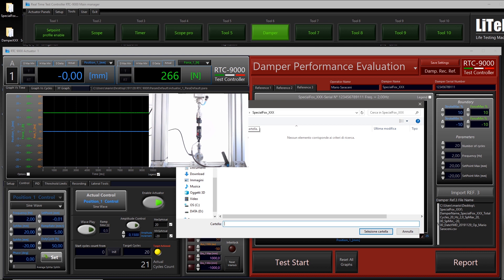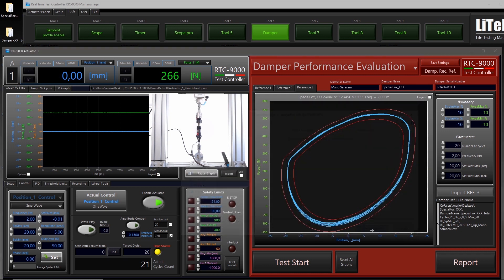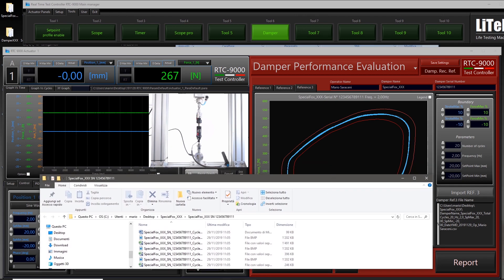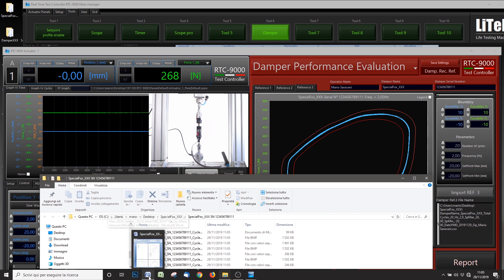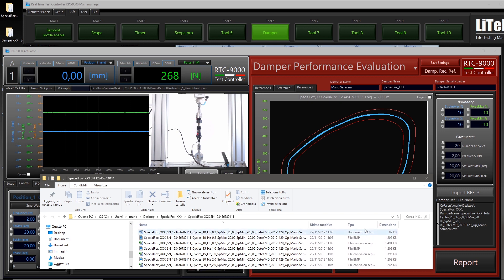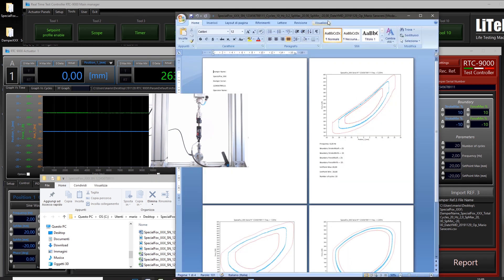Choose a directory where you want to save the report. Inside the reference folder, create a new directory with the actuator name — 'Special Fox XXX' and the serial number — then select it. The report will be created; wait a few seconds. The directory will open automatically. If you have Microsoft Word installed, the report will open; otherwise only images and raw data will be created.